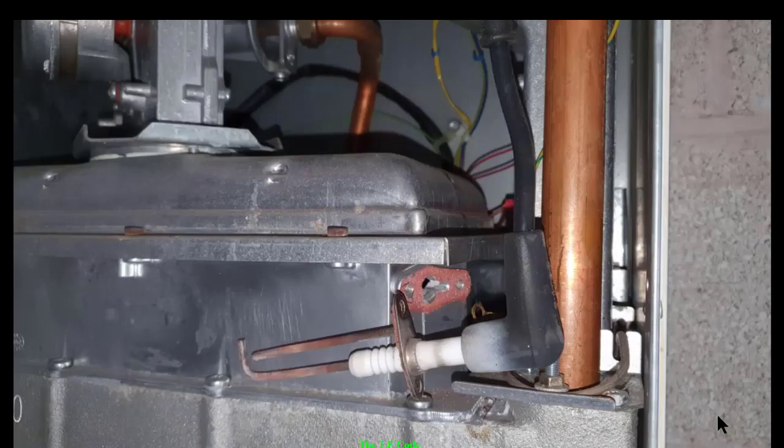Now in this tip, what I'm going to show you here is basically to see if we've got a spark in the first place. So as I said, we've removed the spark electrode and you put it into the holder like this and put it just at the side of the burner, just like we can see in this illustration now. So you turn the boiler on and you watch for the spark. So you see if you've got a good spark coming between the spark gap. Now if you haven't got any spark appearing here, then you could be looking at the spark generator. So as I said, this is your first tip. Do it like this to see if you've got a spark.